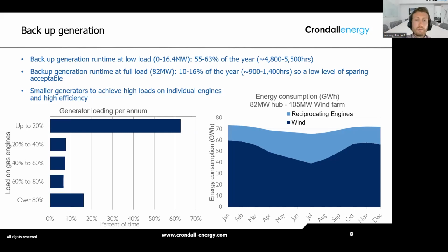The graph on the right shows the loading of our generation installed on board the distribution hub throughout the year. And there's three things I want you to take away from this graph. The first thing is that the backup generation is running at low load, so less than 20%, for about 55 to 63% of the year. So for the majority of the time, we're only needing about 20% of our installed capacity. What that means is we need to install multiple smaller generators rather than having fewer big generators, so that we're in that higher efficiency range on the load factor of those generators.